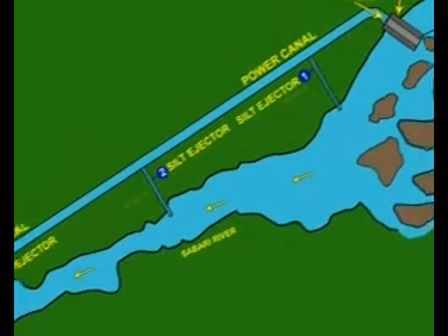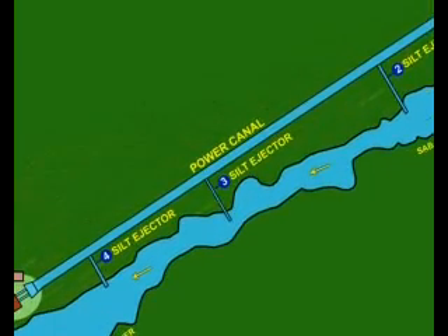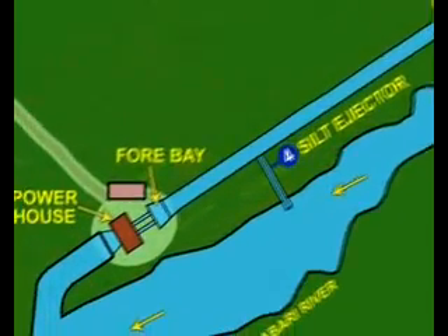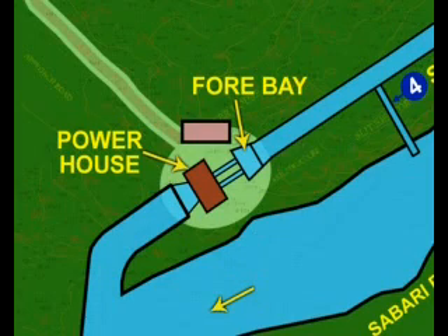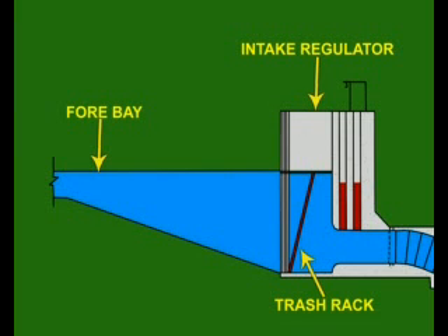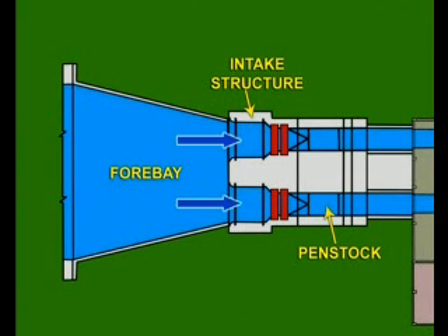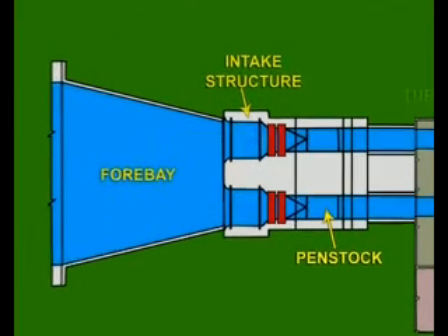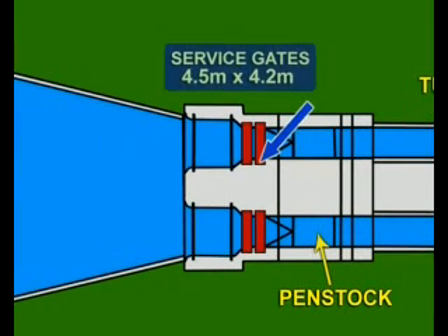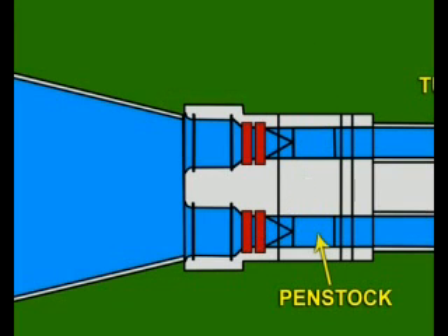The channel will be provided with four numbers of gated silt ejector channels which will help to desilt the power channel. At the end of the channel, a small forebay will be constructed to lead the water flows to the intake structure. The intake structure will have a trash rack to arrest the entry of floating debris into sluice vents. Two sluices are provided in the intake for leading the flows into penstock. Two numbers of service gates of 4.5 meters by 4.2 meters each will regulate the flows into penstocks. Provision for stop log gates is also made in the sluice. A steel transition of 5 meters length is provided at the end of the sluice to provide transition from rectangular to circular.